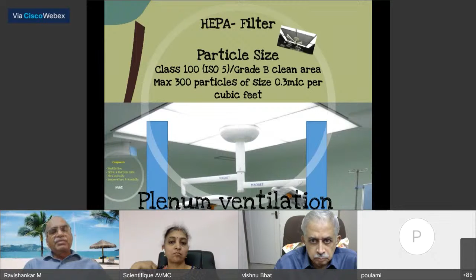Okay, coming next to the particle size, HEPA filters are used in the theaters, and they are to be of class 100 or ISO 5 grade, with a maximum of 300 particles of size 0.3 micron per cubic feet. That is the specification. What is this class 100? What is this ISO? I'll just give a table to explain to you.